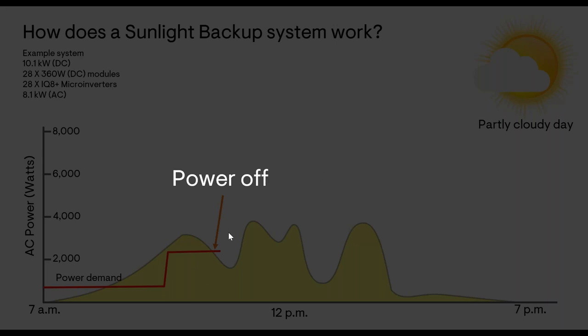In a scenario like this, when the system shuts down because there's too much demand from the house versus what's available from solar, our load controllers are going to turn the system off, and then turn those circuits back on, but one circuit at a time. You might have enough power to turn on one of those circuits, or two, and so on. So it's going to turn them on one at a time. And if it turns on one, then two, and then tries turning on three, but the system shuts down again, it knows to only turn on one and two. It'll periodically test to see if maybe it can get more of those loads on. But it's going to do that automatically for the homeowner.